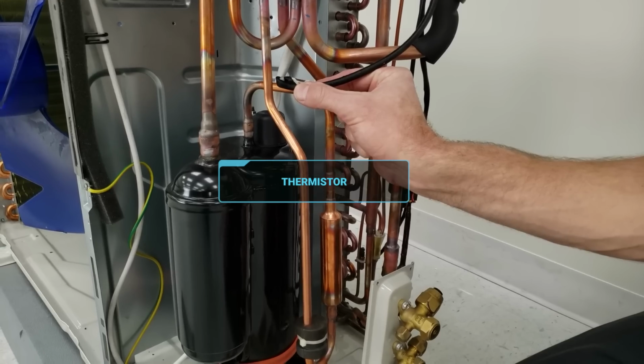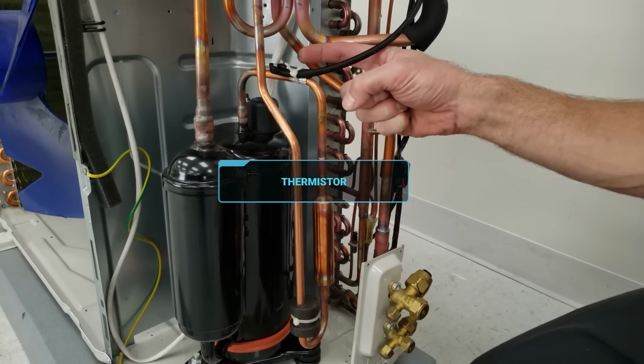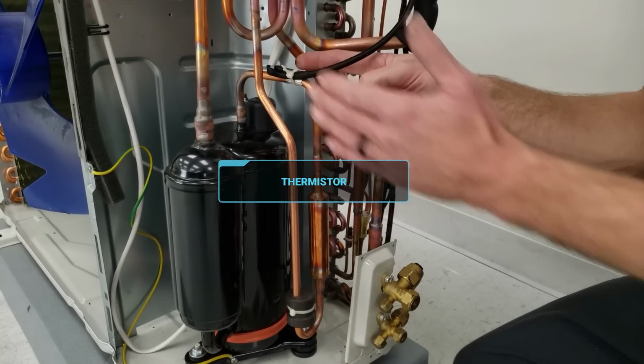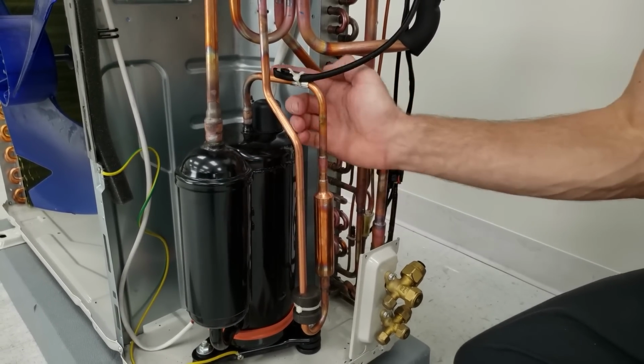If it's a non-hyperheat, you might get maybe 12,000 BTUs of heat, maybe at 20 degrees outside. And so the hyperheat system may allow you to operate at a decent rating down to a lower temperature. But yeah, it's really cool because the system takes many different temperature measurements with the thermistors, and it makes decisions for operation based on these pre-programmed algorithms. What's not cool is we can't see them, and that's what's frustrating.